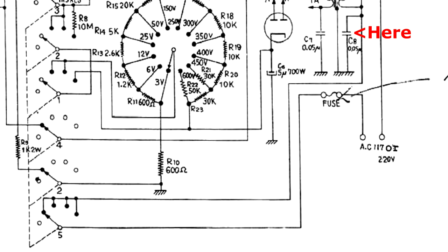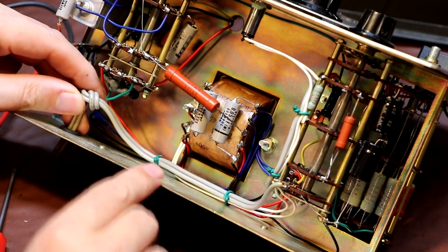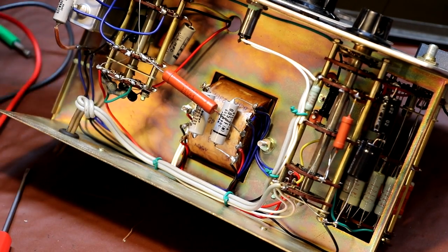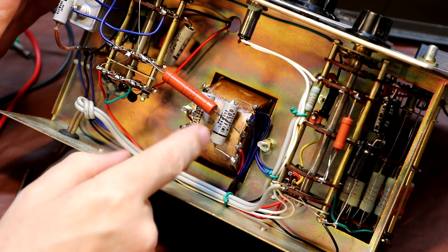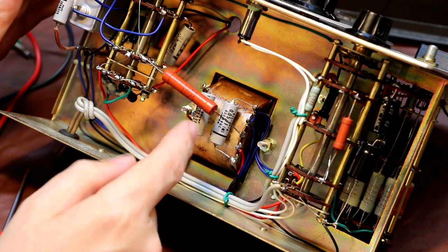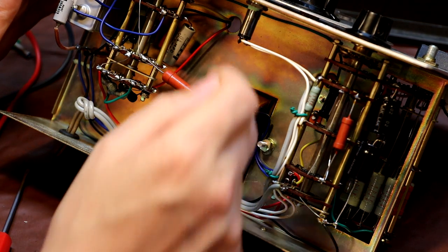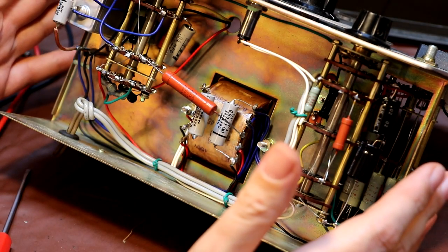But unfortunately the chassis of this equipment isn't actually earthed because it is only connected via a 2-core cable. So the problem is, if this capacitor does develop any leakage, we're actually going to form a connection between the 230 volt supply and the case here, which is going to make the whole piece of equipment live.